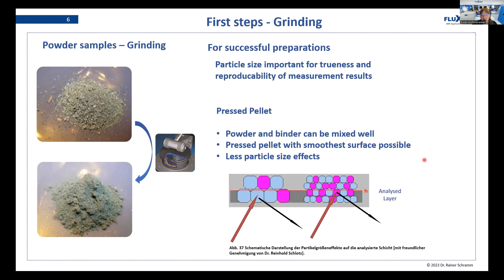The powder and binder for pressing the pellets can be mixed very well, and the pressed pellet will have the smoothest surface possible, which is very good for our measurement afterwards. We will also have less particle size effects. When using XRF, we have something called analysis depth — the fluorescence radiation coming out of the sample only comes from a certain depth. If you have quite big particles, you might analyze only one layer of particles that is not representative for the whole sample. The finer your powder is, the more representative it will be.